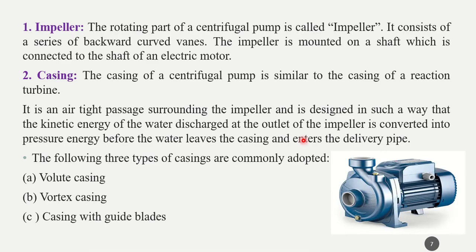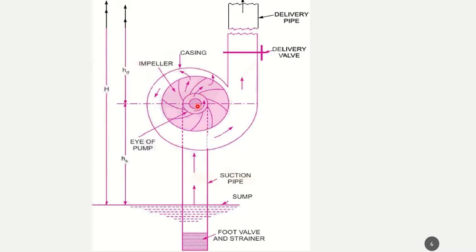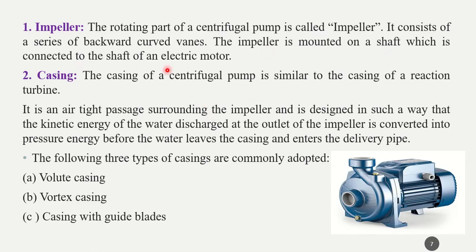Now for a detailed explanation: the impeller is the rotating part of the centrifugal pump. It consists of a series of backward curved vanes. In the diagram you can see the eye of the impeller at the center, with vanes fitted on the impeller that are curved backwards. This impeller is mounted on a shaft which is connected to the shaft of an electric motor — you can see the impeller part and the motor shaft in the diagram.